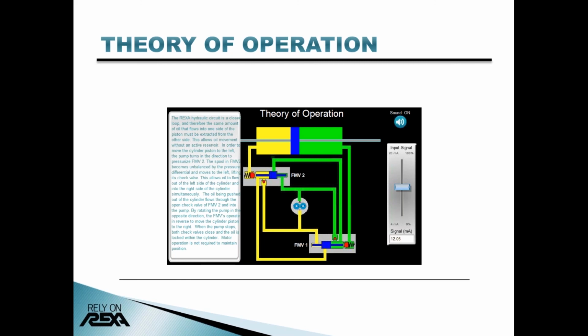During operation, when the actuator is at the desired position, spring-loaded ball check valves are locked in place to prevent the flow of oil through the flow match valve. But when there's a signal change, the motor activates, turning the bidirectional gear pump, which instantaneously builds pressure, allowing the ball checks to open. The oil is then transferred through the flow match valve from one side of the cylinder to the other, or one side of the rack to the other for rotary motion. Once the actuator has reached its desired set point, the motor stops and the ball checks are seated, stopping the flow of oil through the system.